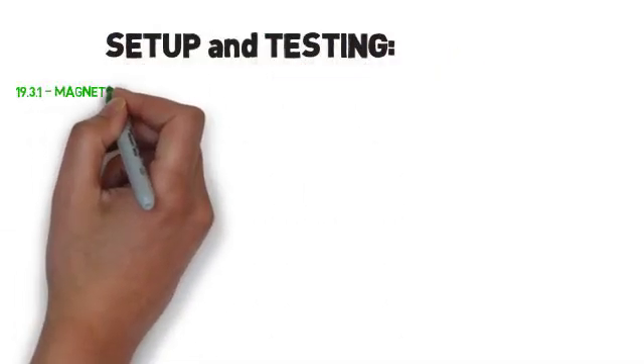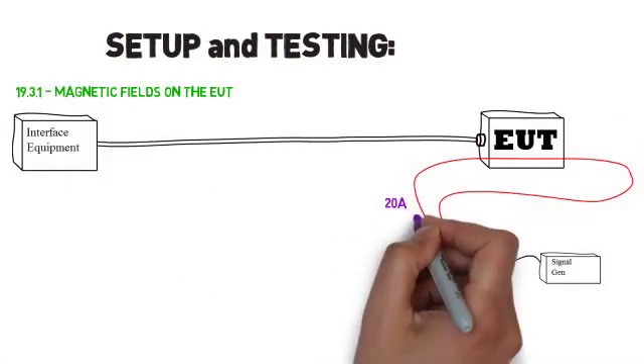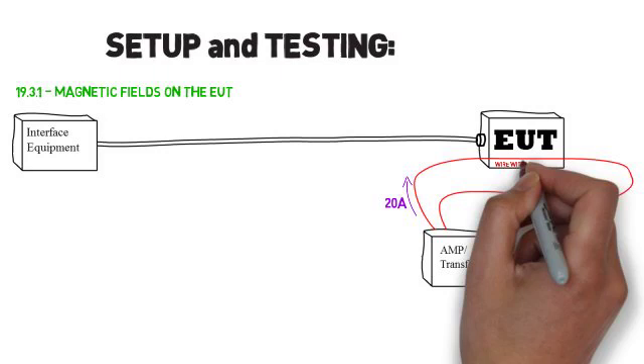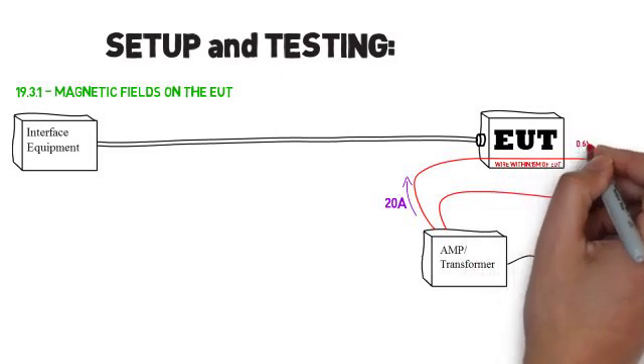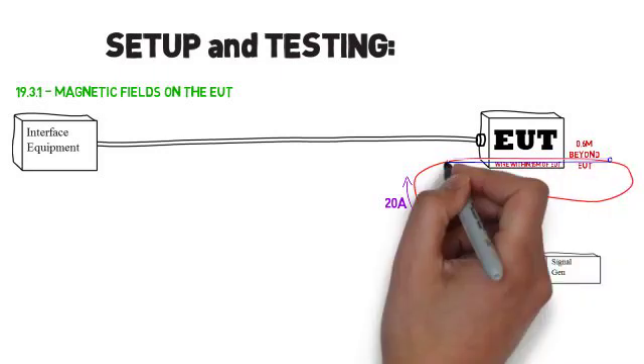Magnetic fields is simply executed by running 20 amps at 400 hertz through a straight wire located within 0.15 meters of the EUT. The wire must extend 0.6 meters beyond each extremity of the EUT. This can be accomplished by simply sticking a wire through PVC piping for ease of handling.